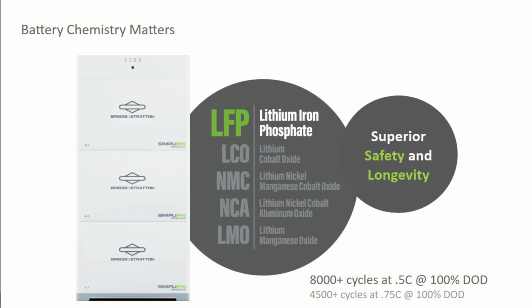Lithium ferrophosphate has very long duration. So to answer the question you had earlier, how long do these batteries last? We can get somewhere in the range of, starting at the bottom, 4,500 cycles up to 10,000 cycles. A cycle is how many times you charge and discharge a battery. The cycle life depends on how deeply you discharge it and how quickly. So cycle life is a number we use, but it's sometimes hard to quantify.